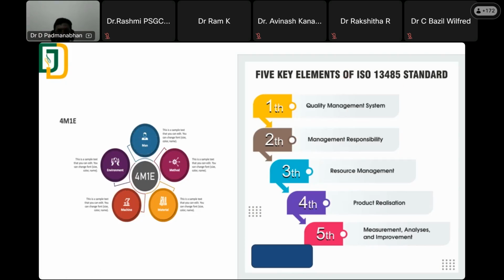But in the case of 13485, for all your people who are working in a medical device organization, right from the base level as a worker to your organization head, it is defined how they should be and what education qualification is required. Secondly, the method you are adopting for manufacturing your medical devices needs to be standardized, optimized, and validated. Until this is done, you may not be provided with the 13485 certification. Similarly, whatever material is being used for manufacturing your medical devices needs to be evaluated and assessed. Only qualified material should be placed in your manufacturing process. The same is applicable for a machine.